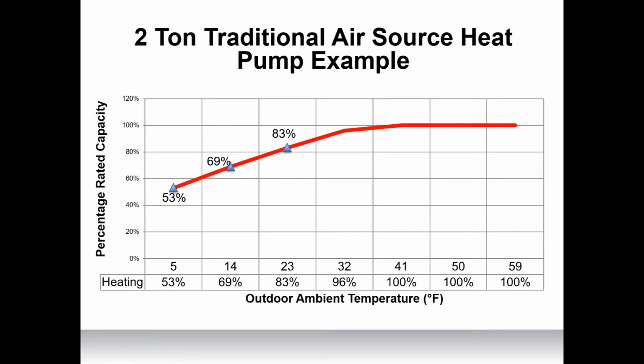We want to dig in a little bit deeper. Let's take a look at the heating capability of a 2-ton traditional VRF air source heat pump. So this is a VRF system. It has the inverter compressor, but it's a traditional heat pump, not a cold climate system. As we can see, this heat pump's ability to provide sufficient heat begins to drop off once we get below freezing. I certainly wouldn't want to have this as a primary heat source in my home here in Chicago, right? Would this be okay if I lived in Dallas, Texas? Yes. Is this okay if I live in Detroit, Michigan? No. I am actually derating enough that here at 5 degrees, I'm giving approximately 53% of my heating capacity. That's okay for supplemental or shoulder season heating here in the Midwest, but not as a primary source of heat.